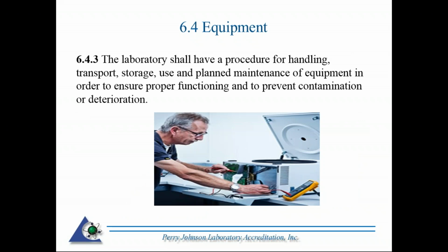The laboratory shall have procedures for handling, transport, storage, use, and planned maintenance of equipment in order to ensure proper functioning and to prevent contamination and deterioration. And so I'm depicting a centrifuge there. Often I come across this with laboratories referring to the manufacturer's manual, manufacturer's protocol for planned maintenance of equipment. This is crosswalked directly over from the 2005 standard.